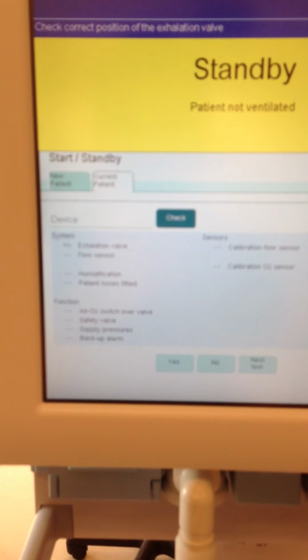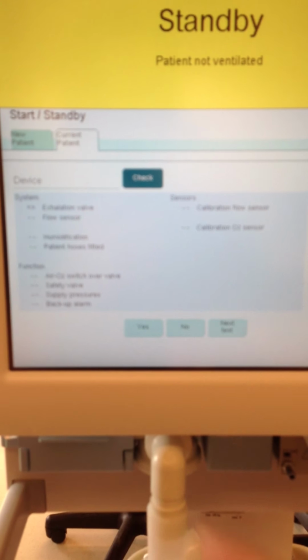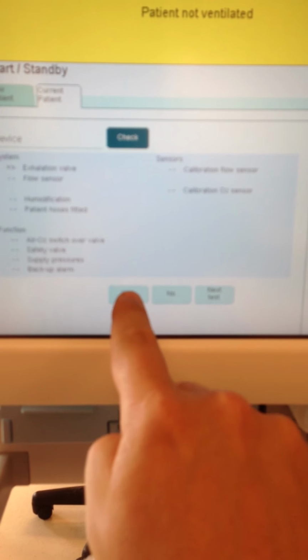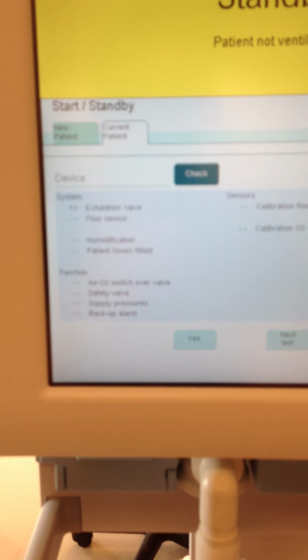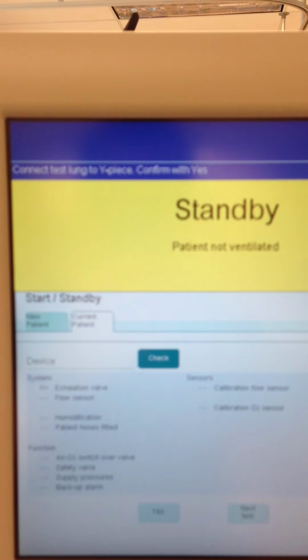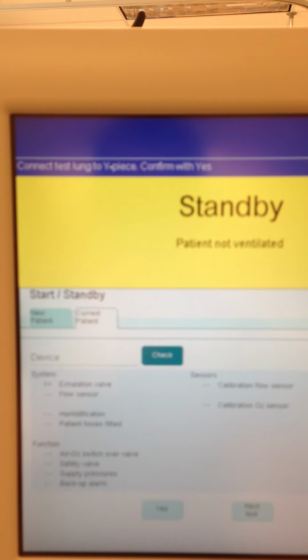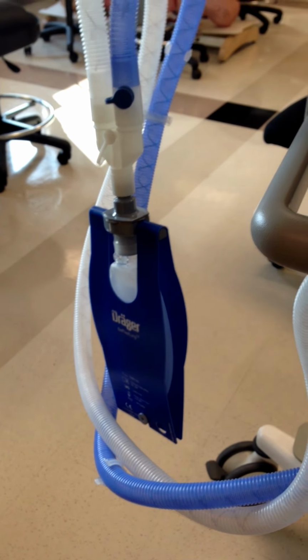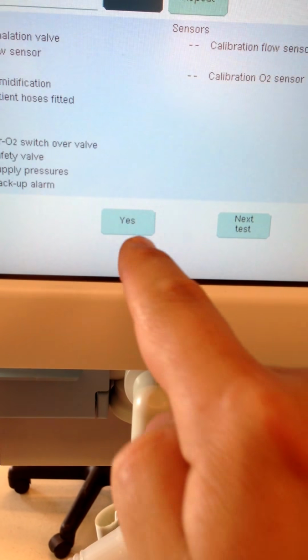You'll notice over on the right side there's a counter, so it times out if you wait too long or if you get called away to another patient to do something. So we've checked this, so we're going to go ahead and hit yes. What it's going to do now is it says connect test lung to the Y piece and confirm when you've done that with yes. Alright, so you can see we've connected our test lung, and we're going to come back now and simply select yes.